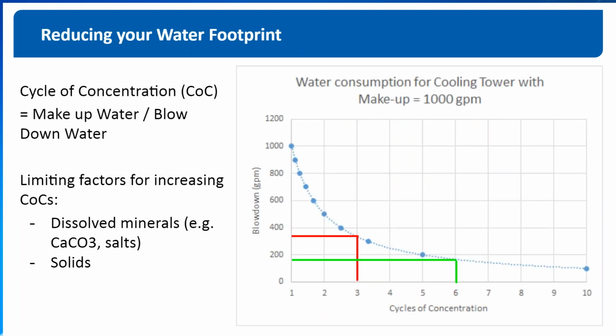One of them, of course, being the water footprint, and this is becoming more and more important. Now, the easiest way to save water is to increase cycles of concentration, especially if your site is running at low cycles to start with. Increasing cycles from 3 to 6 reduces cooling tower makeup water by 20% and cooling tower blowdown by 50%.